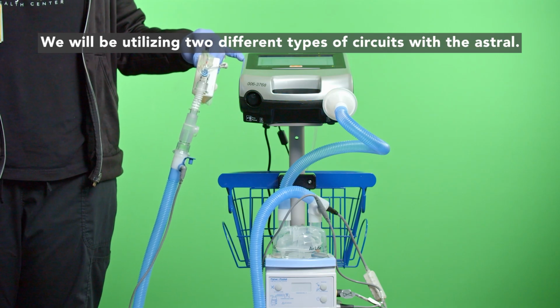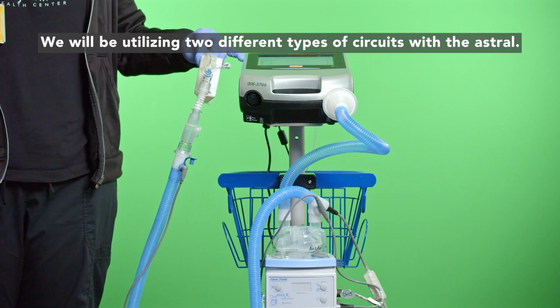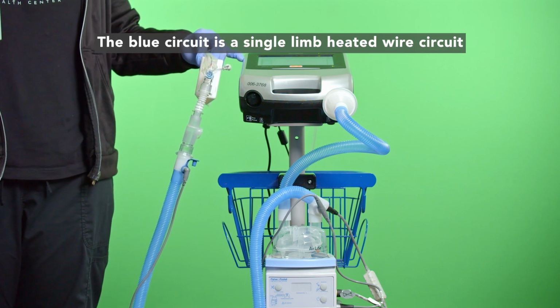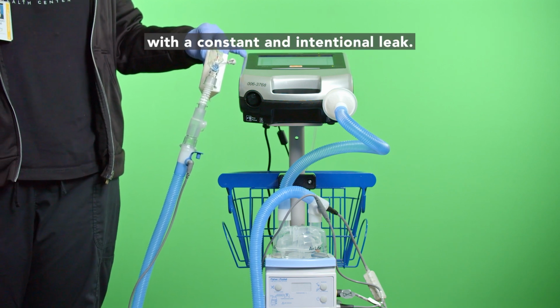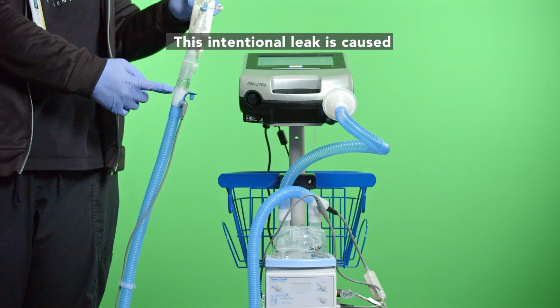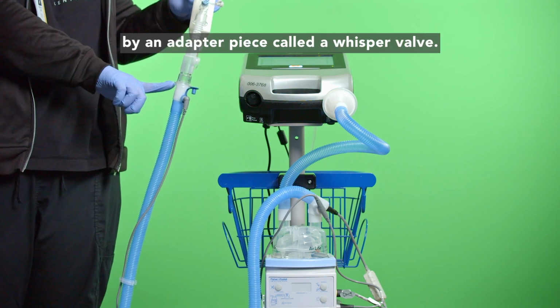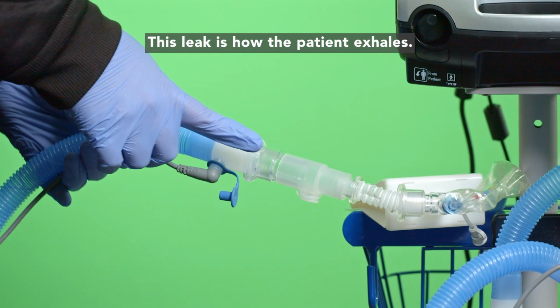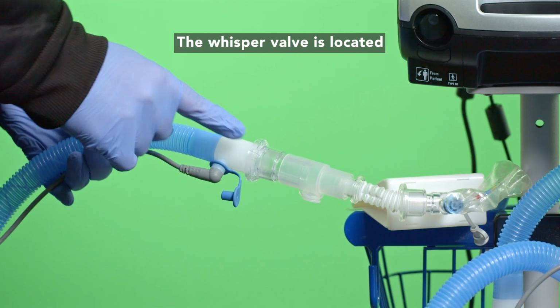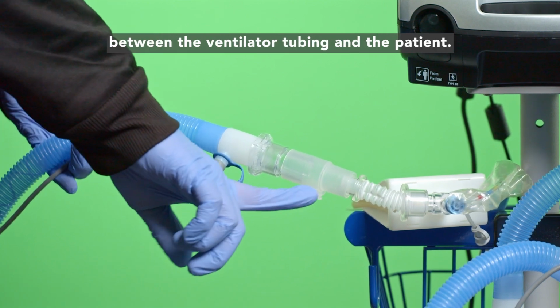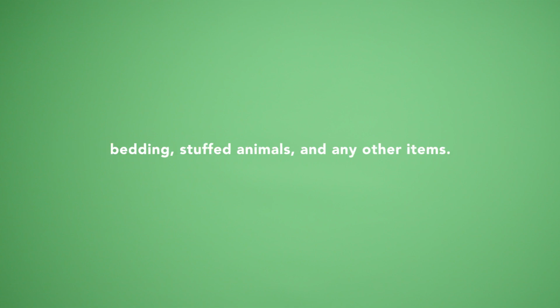We will be utilizing two different types of circuits with the Astral. The blue circuit is the single limb heated wire circuit with a constant and intentional leak. This intentional leak is caused by an adapter piece called a whisper valve. This leak is how the patient exhales. The whisper valve is located between the ventilator tubing and the patient. It is important to keep the whisper valve exposed and free of bedding, stuffed animals, and other items.